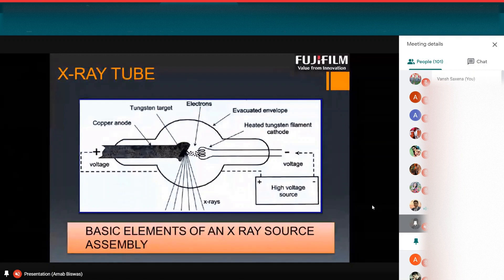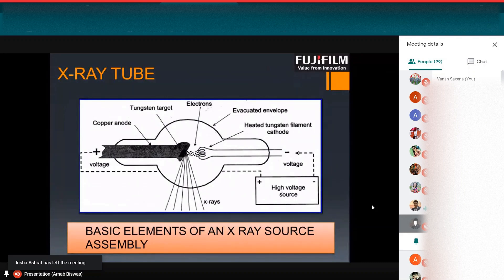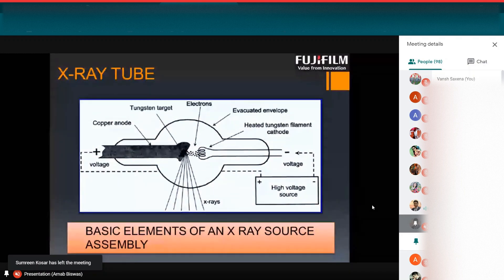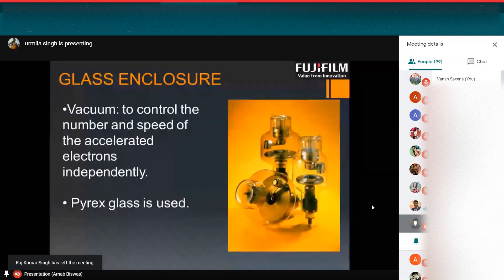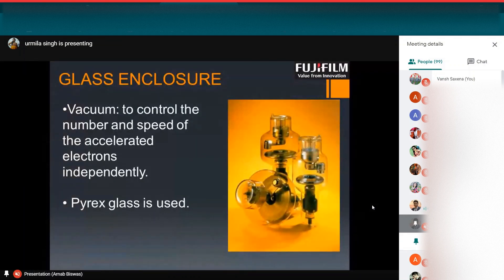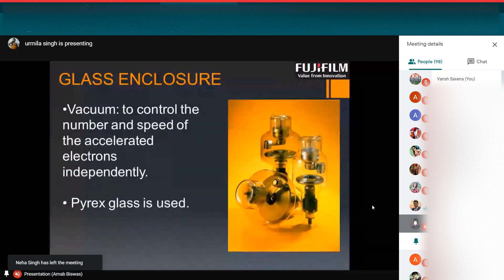This cathode and anode is placed inside an evacuated envelope. Why we place this in an evacuated envelope? Because it is to control the number and speed of accelerated electrons independently, so that the outer atmosphere cannot hamper this situation. Like the outer things like humidity or other electromagnetic waves, these things can hamper the control of the number of processes and accelerated electrons independently. Pyrex glass we use as an envelope, as a glass envelope.